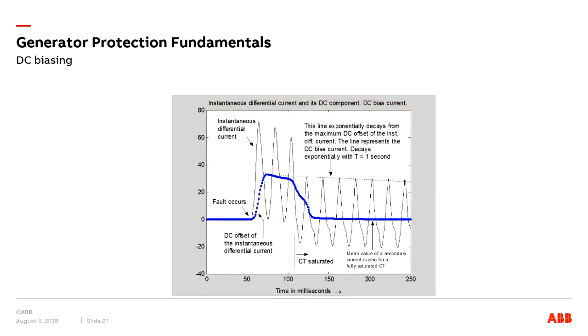And also the DC biasing. In the case of a fault with a very long DC time constant, there is a risk of saturation of a CT feeding the generator differential protection. To minimize the risk of unwanted trip due to this DC current saturation, there is a possibility to have a DC-current-dependent bias contribution with a slow decay, or to desensitize the protection temporarily in such a situation. So you can see from here the CT is saturated because of the DC constant.